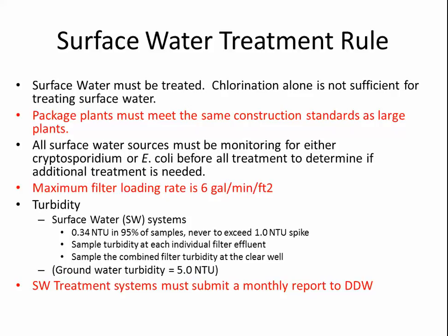All surface water sources must be monitored for either Crypto or E. coli before treatment to determine if you need additional treatment. And then it's important for the test, if you have filters, to remember that the maximum filter loading rate is 6 gallons per minute per feet squared.